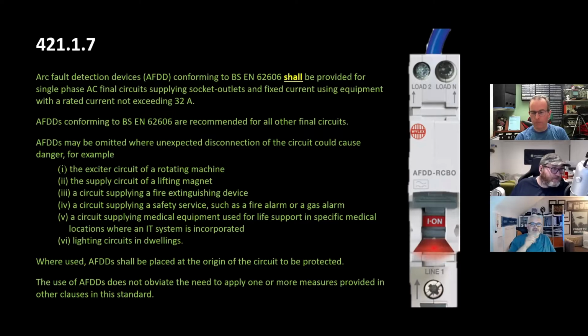There's a surprise. AFDDs conforming to BS EN 62606 are recommended for all other final circuits. However, AFDDs may be omitted where unexpected disconnection of the circuit would cause danger, for example the exciter circuit of a rotating machine.